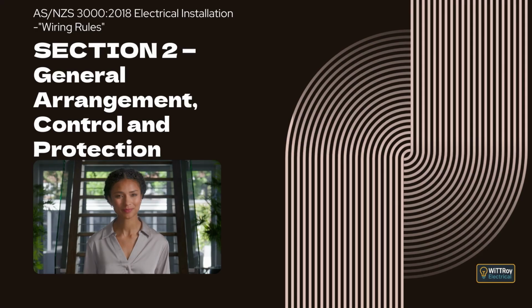Some circuits must not be interrupted because the loss of power would create a greater danger than overcurrent itself. These include some safety system supplies, lifting magnets, or certain control circuits. In these situations, the design may require special alarms or monitoring systems instead of disconnecting the supply automatically. Another exception allows protective devices to be placed at a different location when permitted by other clauses in the standard. In some cases, protection may be omitted if allowed by later clauses in Section 2.5.3 or 2.5.4.